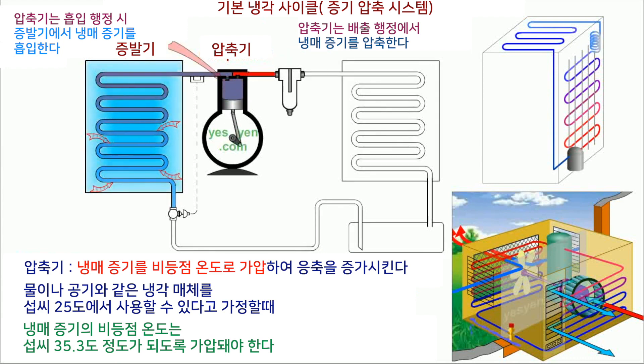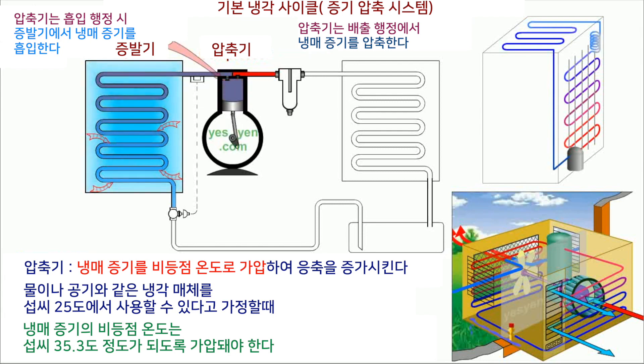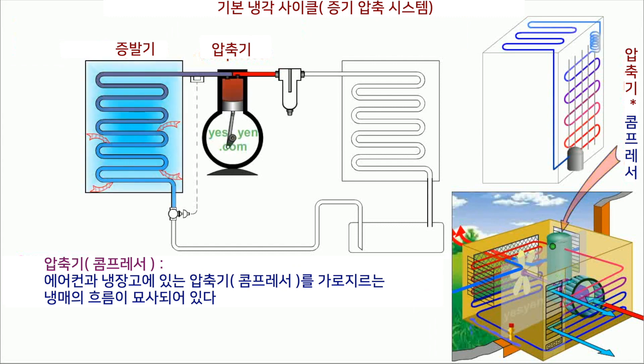Compressor: The compressor pressurizes and hence increases the condensing — that is, the boiling point temperature — of the refrigerant vapor. Assuming a cooling medium like water or air available at 77°F (25°C), the vapor has to be pressurized such that the corresponding condensing temperature is around 95°F (35°C). The flow path across the compressor in the air conditioner and refrigerator is depicted.